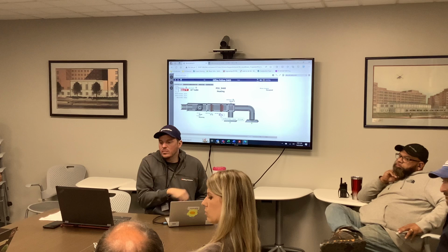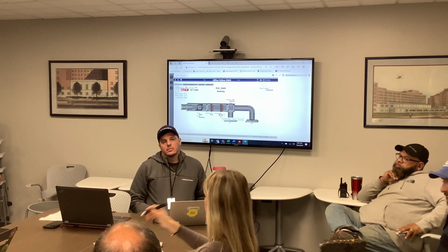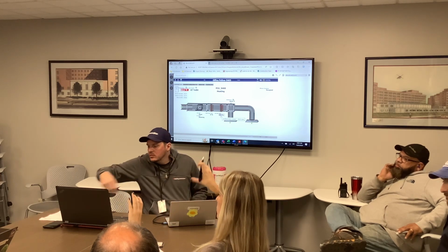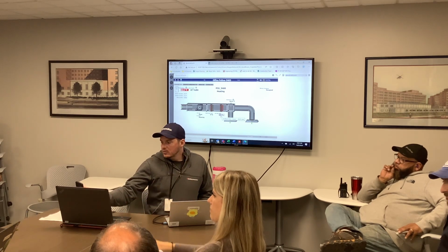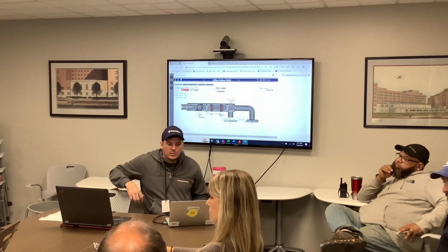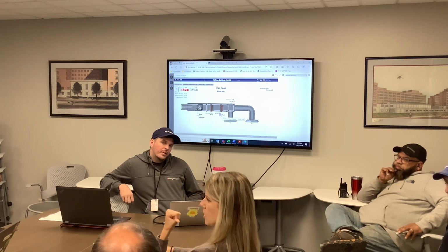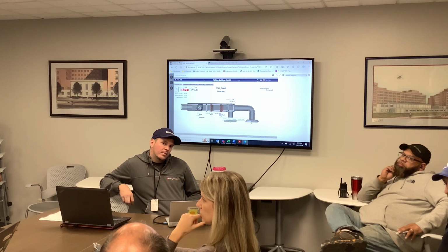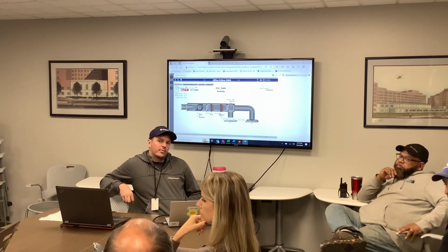So right now, the fan coil units that are closer to the hall, those have the dual temp, but it's kinda weird, it's like the way the wing is, this part is connected to the mechanical room. Are the fan coils on and off sequence due to set point? Correct, yeah, they cycle. So I think that's where we had the issue, because we had the pneumatic stats, if the rooms were calling for heat, and we didn't have it, the fans were shut off.